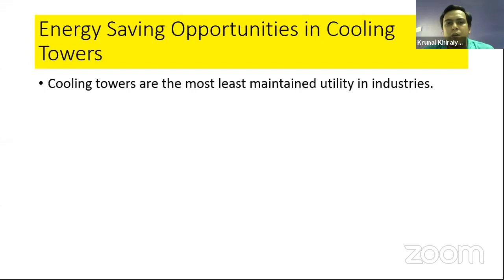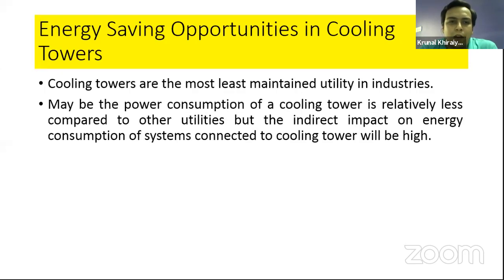So what energy saving opportunities are available in a cooling tower? First, why is this topic very important? Because if you go into industry, cooling towers are the least maintained utility. Nobody takes care of the cooling tower because all the people think this is not an important utility, and that's why they are not giving too much importance to it. Maybe the power consumption of the cooling tower is relatively less compared to other utilities, but the indirect impact on the energy consumption of the systems connected to the cooling tower will be high. That's why you need to focus on the cooling towers.